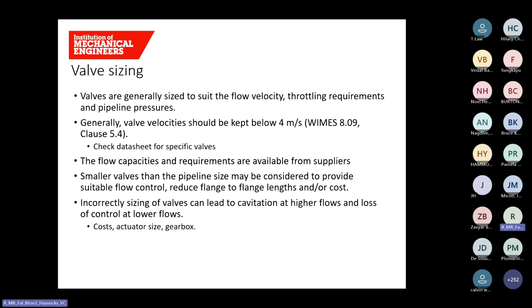Smaller valves in a smaller pipeline can be used. So if you're trying to restrict or throttle the flow, sometimes it makes commercial sense to reduce the pipe diameter and therefore the valve size. Not only does this potentially give you better control, but it also reduces the size and therefore the cost of the valve. It also reduces the overall length, the flange to flange distance of the valve, which can be useful sometimes.